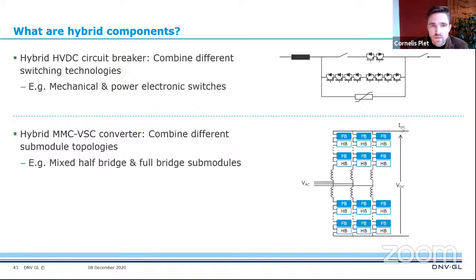The last type of component I would like to discuss is a hybrid MMC VSC converter. This is a multi-level modular converter, which combines half-bridge modules, which have relatively low cost and could be seen as efficient and reliable, with full-bridge modules, which have a high fault current blocking capability and reduced voltage operation capability, depending on the ratio between half-bridge and full-bridge modules. As such, they could be an alternative for HVDC circuit breakers in what we call non-selective fault clearing schemes. Many purely half-bridge based converters are already in operation, and the first fully full-bridge converters are in development, Ultranet. The main challenge in making a hybrid half-bridge, full-bridge converter is how you energize and charge the submodules in such a converter.